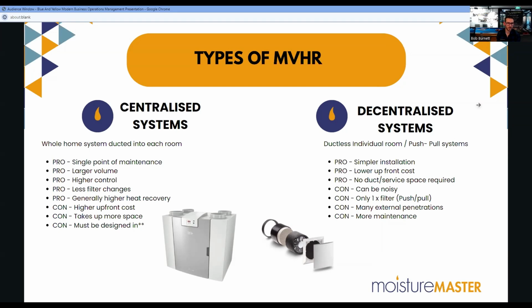So pros of the centralized system are a single point of maintenance. They've got larger volumes, generally higher controls, and fewer filter changes, in that we've just got the filter changes on the unit rather than lots of different filter changes for different fans. We've got higher levels of heat recovery. Some of the cons of a centralized system: they're a higher upfront cost, they take up more space generally, and they really should be designed in upfront. It's really hard work to try and squeeze a centralized system into a home that hasn't had it designed in, or trying to squeeze it in after it's gone through consent down the line.